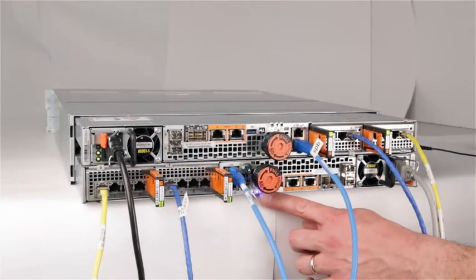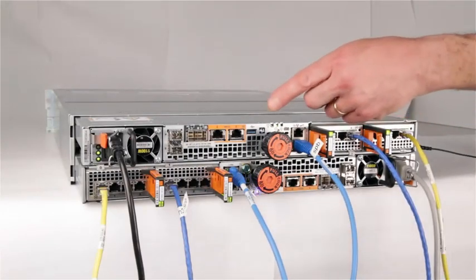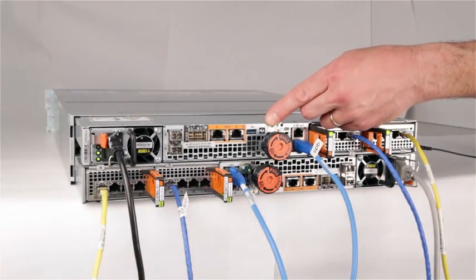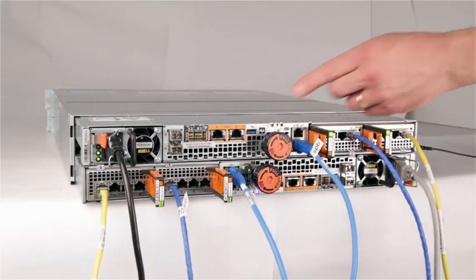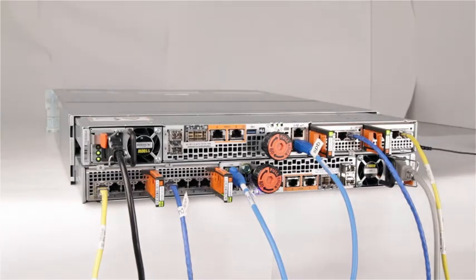Here we can see that SPA is in Service Mode. Also notice that the Unsafe to Remove LED is illuminated on SPB. Make sure that you do not remove an SP with the Unsafe to Remove LED illuminated.